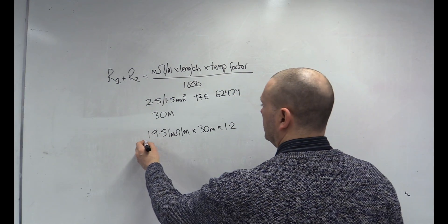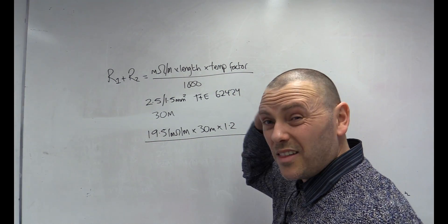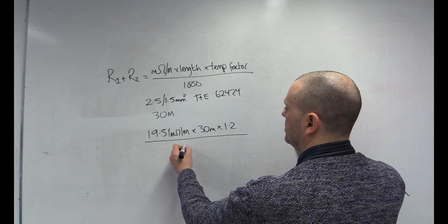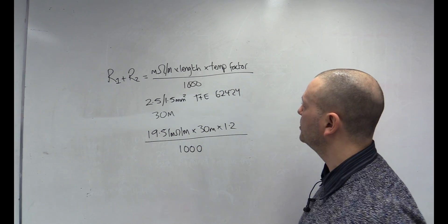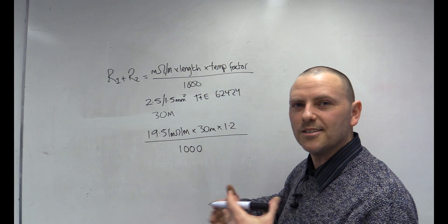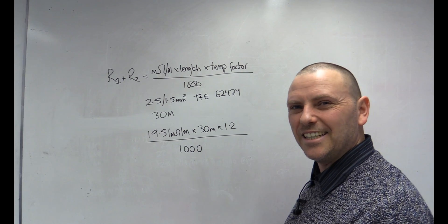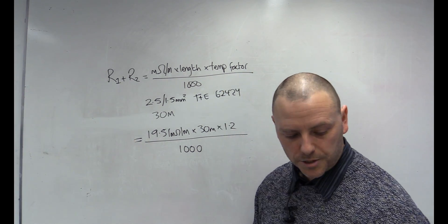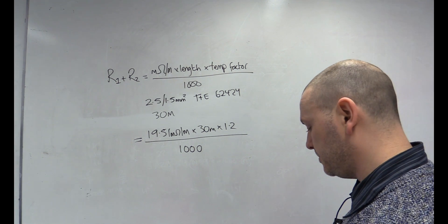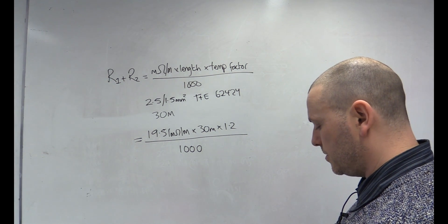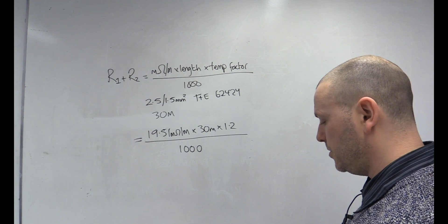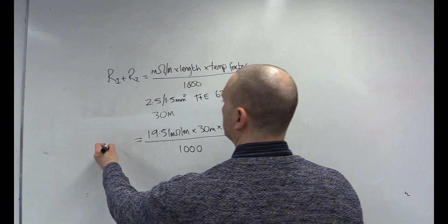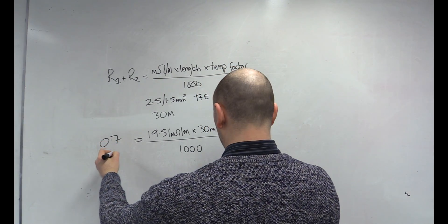It's a real cheat, that is. The alternative is that it's not that hard, the other equation, but it's a little bit trickier and it takes longer. So, we've got to be thankful for the people that have kind of come up with these equations and the factors and the tables. It takes a bit of getting used to, but actually it saves you loads of equations. So, let's see what the R1, R2 is for that circuit. 19.5 times 30 times 1.2 divided by 1,000. So, our R1, R2 would be 0.7 ohms.